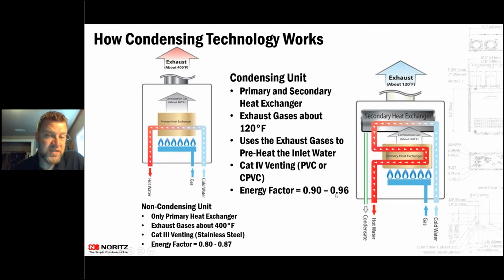I know in 2018, they changed everything from an energy factor to a uniform energy factor. So when you see data plates on tankless, tank, anything that's out there right now, it should show a UEF rating and not an EF rating. So the UEF rating is where everything is moving forward with all appliances now.